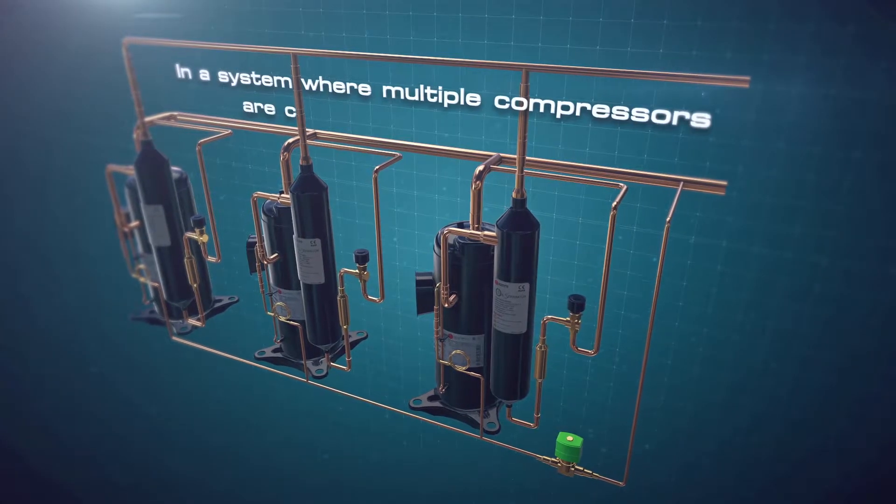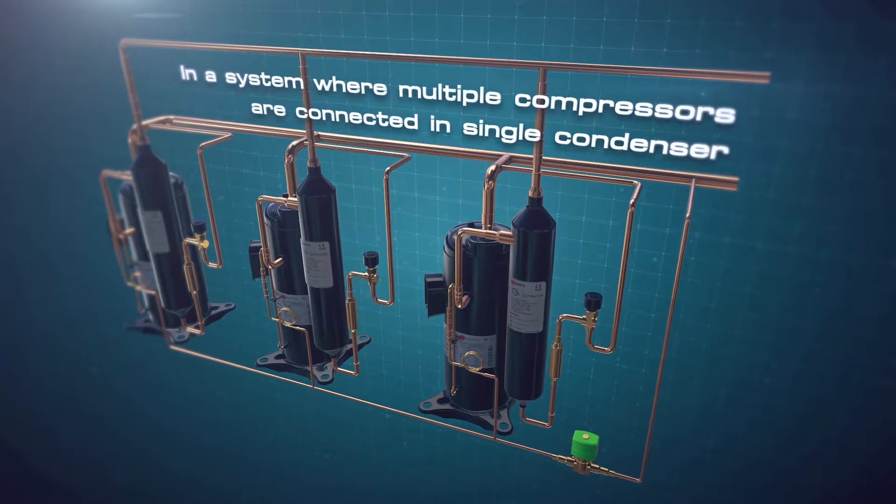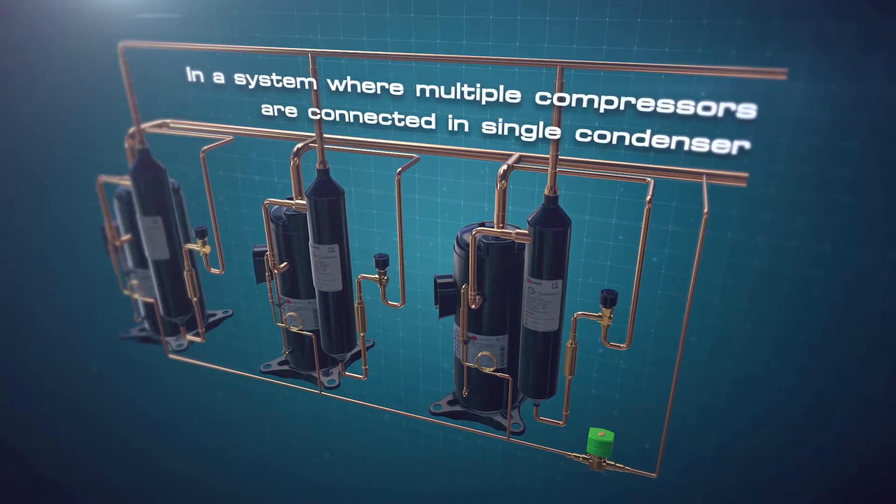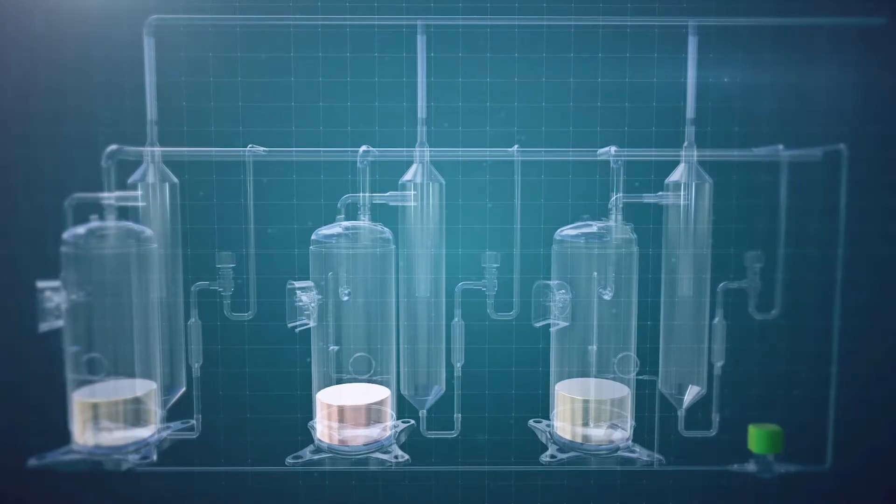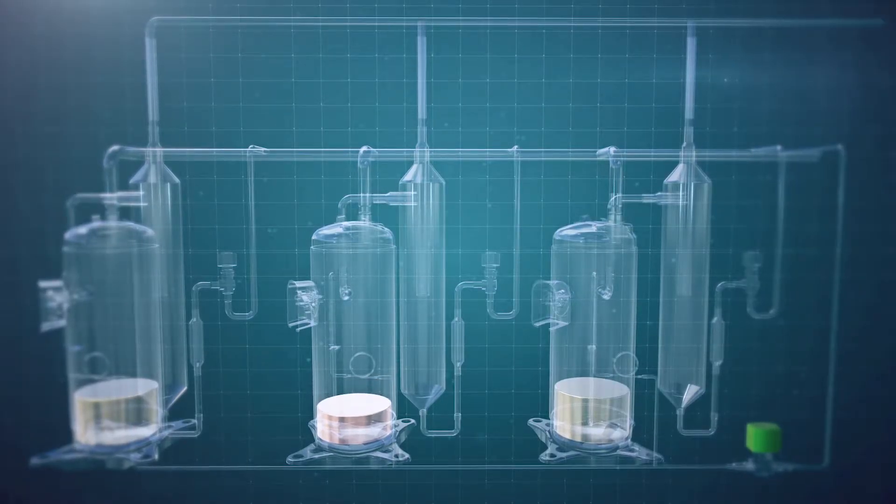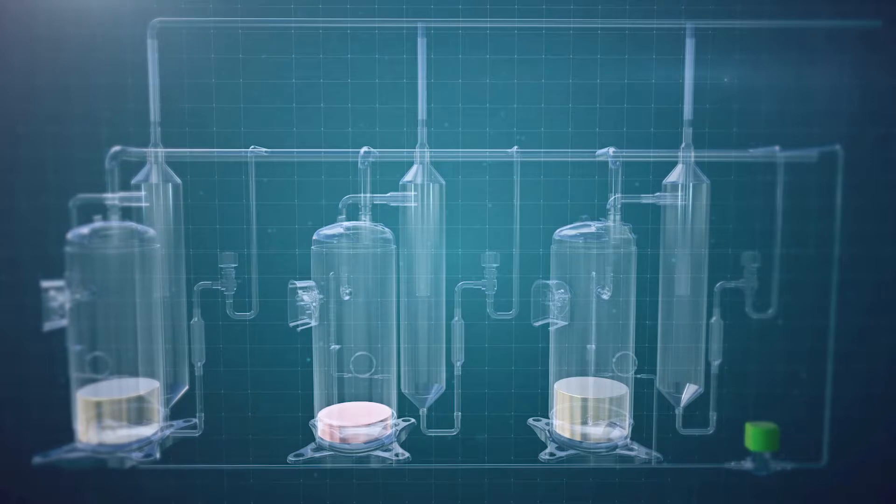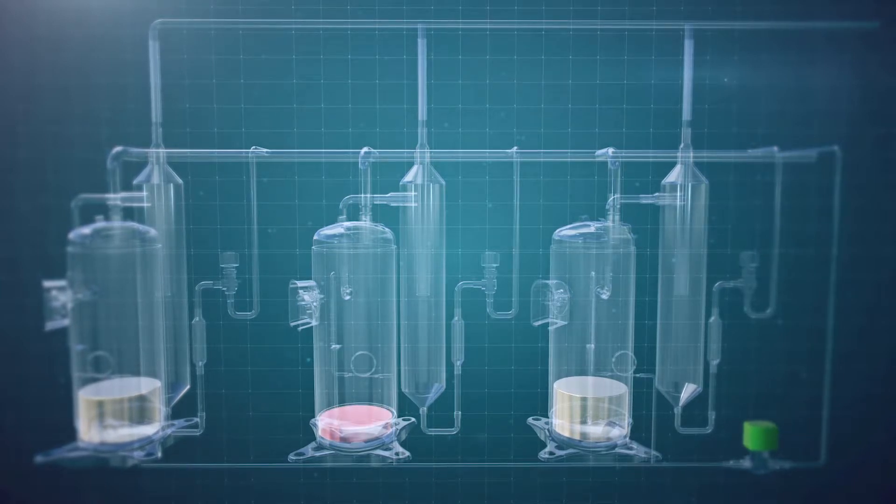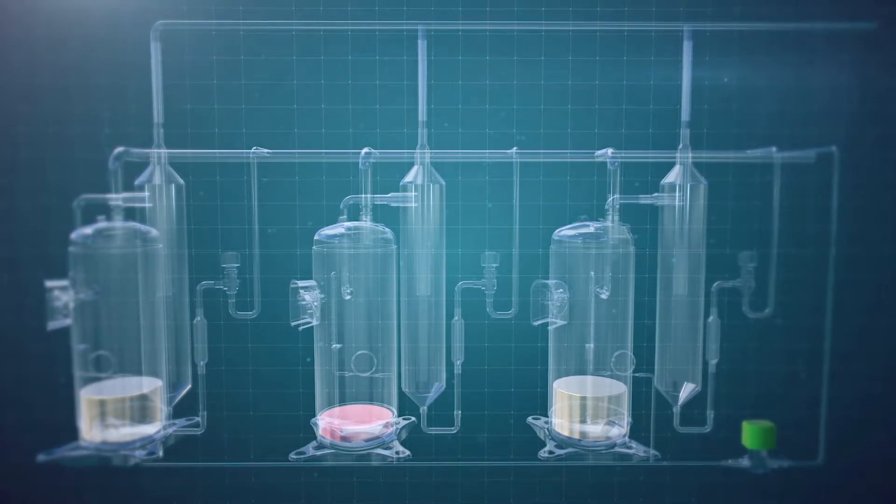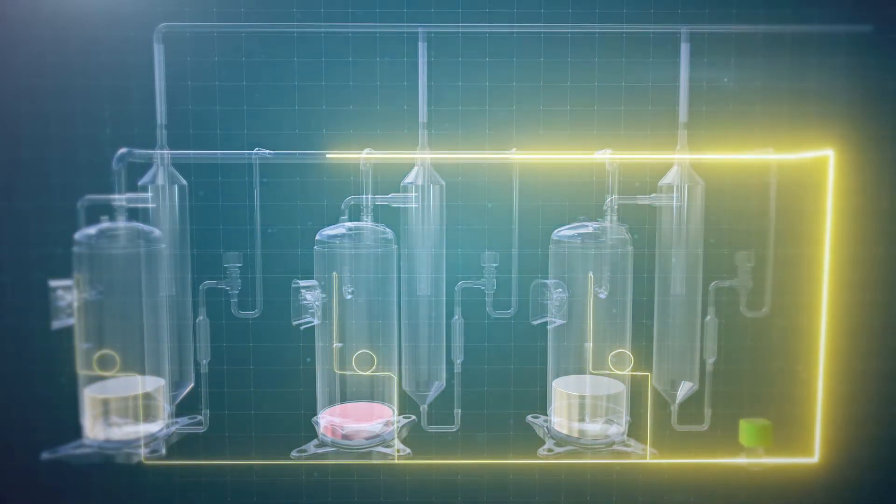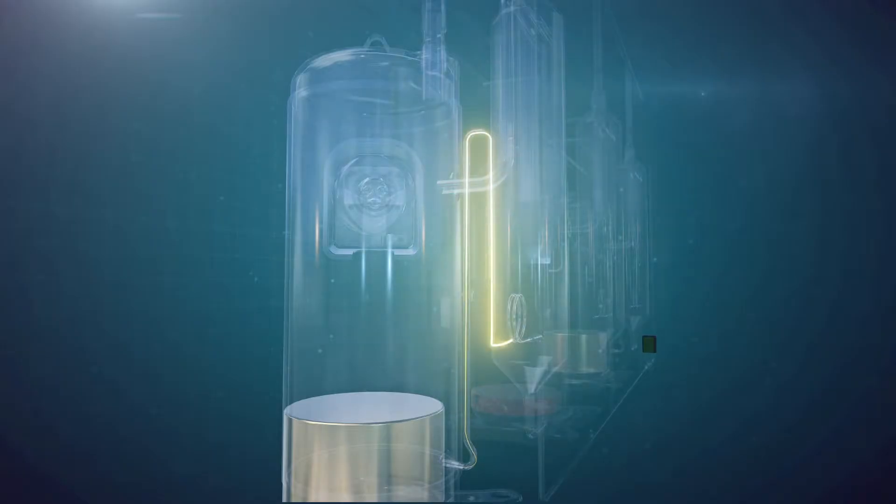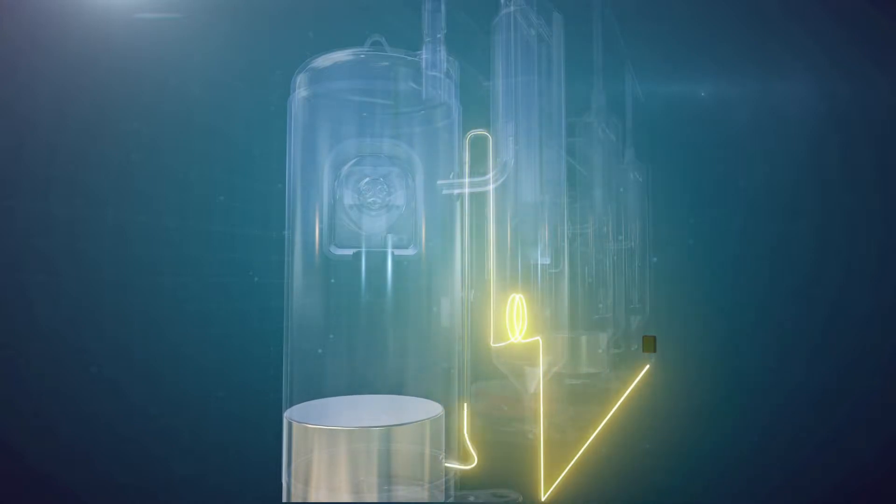In a system where multiple compressors are connected in single condenser, the connection plan is as shown. Due to multiple compressors working simultaneously, the oil level in some compressors are prone to be lower than the optimal level. The oil balance technique manages the oil level by regulating the solenoid valve openings in a timely manner to keep the oil level of all compressors at optimum.